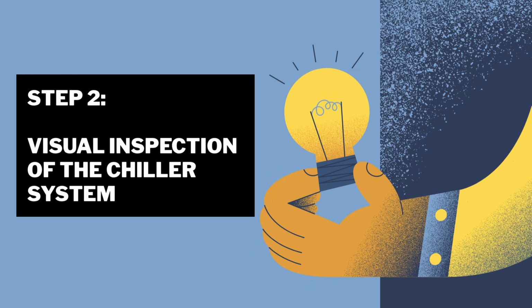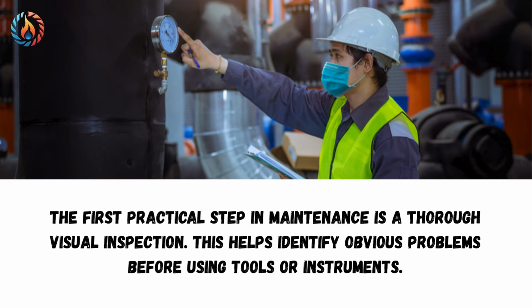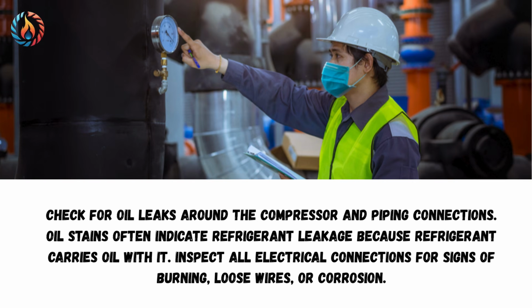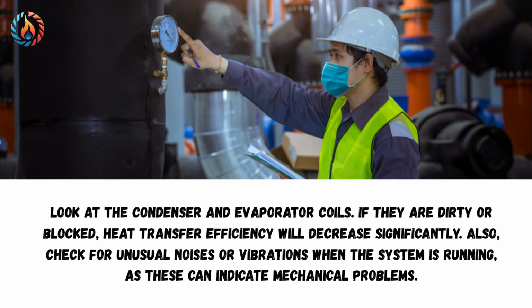Step 2. Visual inspection of the chiller system. The first practical step in maintenance is a thorough visual inspection. This helps identify obvious problems before using tools or instruments. Check for oil leaks around the compressor and piping connections. Oil stains often indicate refrigerant leakage because refrigerant carries oil with it. Inspect all electrical connections for signs of burning, loose wires, or corrosion. Look at the condenser and evaporator coils. If they are dirty or blocked, heat transfer efficiency will decrease significantly. Also, check for unusual noises or vibrations when the system is running, as these can indicate mechanical problems.